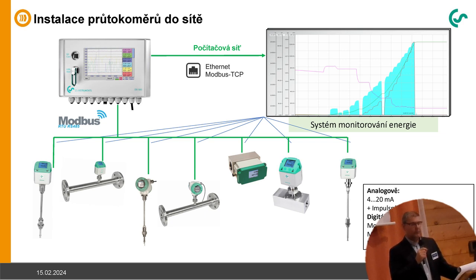But nowadays, all the people want to connect the sensors to their PLC system or to their computer network. And therefore, all the sensors are available with the Modbus RTU, RS485 interface. Some of them also with a Modbus TCP, Power over Ethernet interface. Some of them, or all of them, with the M-Bus interface. M-Bus is a so-called metering bus, especially for energy monitoring systems. That means you can connect all the sensors to the company's network. They get their own IP address, and all the values can be transmitted to a server or to a computer software.